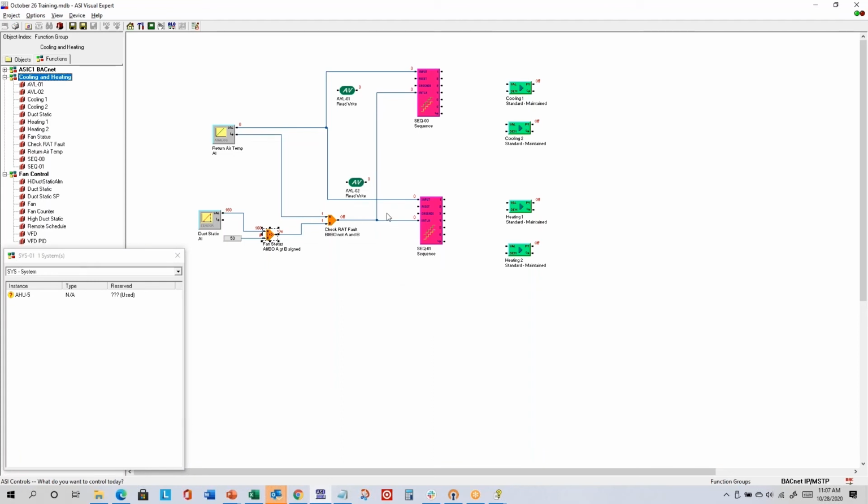So now I'm going to put these base set points in. When I have multiple stages for sequences, I like to have one base set point that's adjustable from the front end so that all the set points shift together. You can have individual set points for each stage, but I've found that that's not so user-friendly because the users won't tend to keep them with the same offsets.